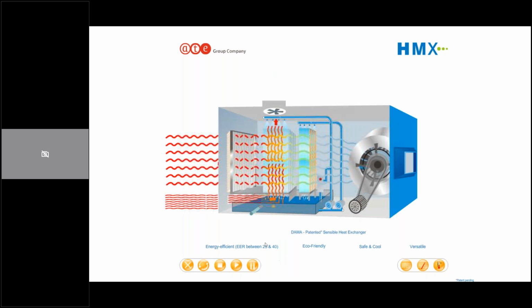This is how it happens. These are two counterflow systems, and this is where the heat exchanger happens. This air stream, which is going into our room, is only sensibly cooled. It doesn't get any moisture added. In the alternate passage, you have the exhaust stream going through. This exhaust fan sucks the exhaust air through.